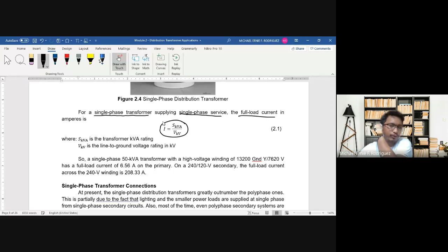Okay, so for a single phase transformer supplying single phase service, your full load current is computed using this formula: simple power formula, I equals S in kVA over V in kV. Your S is the transformer kVA rating, and your V is the line to ground voltage rating of the transformer, in kV.